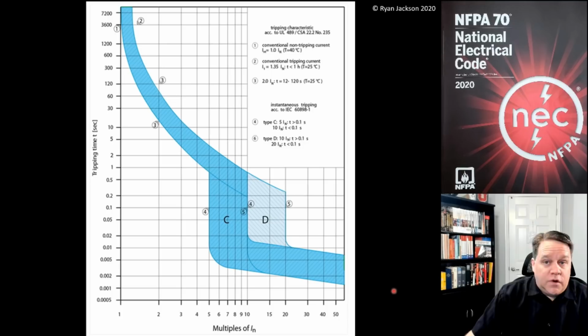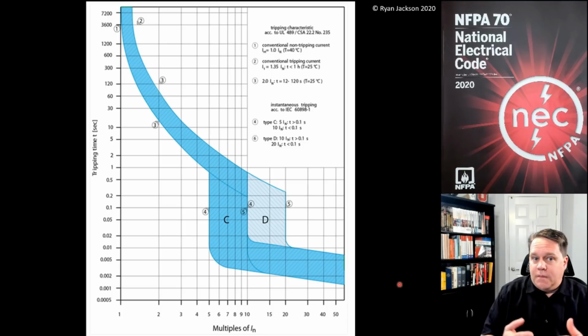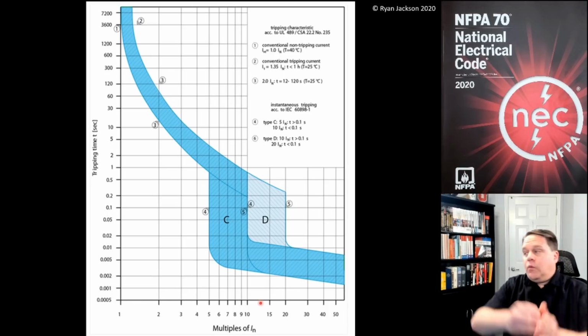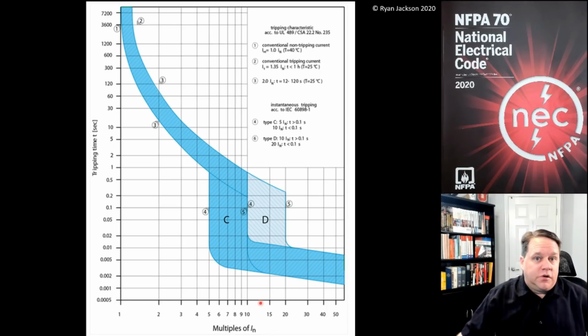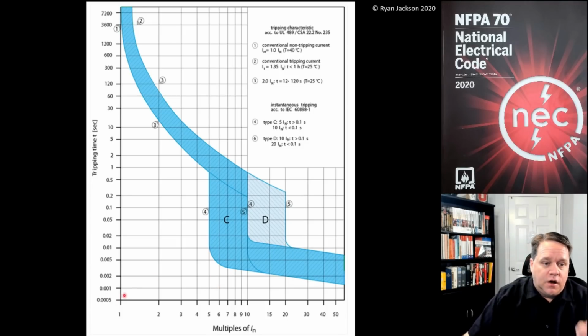This is a logarithmic scale. So what I mean by that is, if we wanted the same distance between the 1 and the 2 and the 2 and the 3 and the 4 and the 5, we'd have a 100-foot wide and a 100-foot tall piece of paper to do it. Okay, so this is done in a logarithmic scale. So the concept here is this. On the bottom, I have the rating of my breaker measured in multiples. So if I have a 20 amp breaker times 1, which is 20 amps, how fast will it open? Well, if I move up here, the answer is it never will, because it's not supposed to.